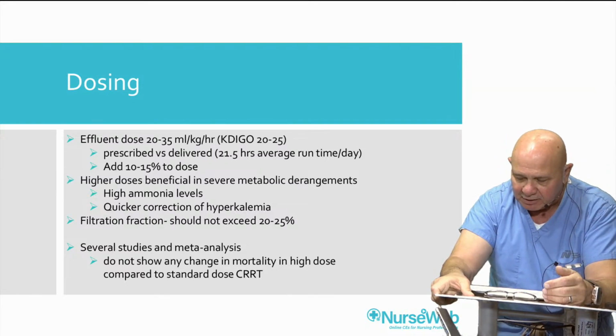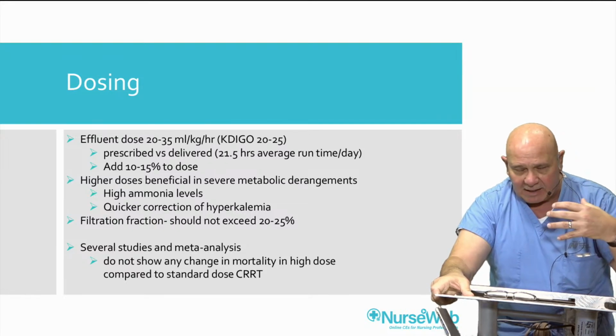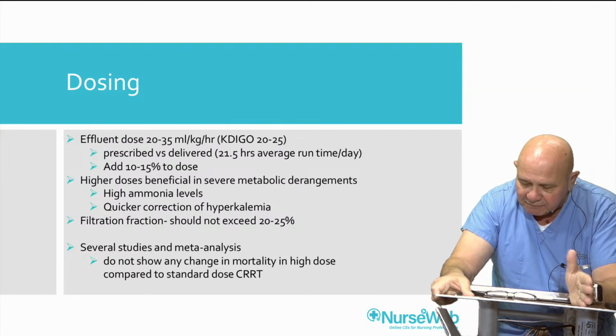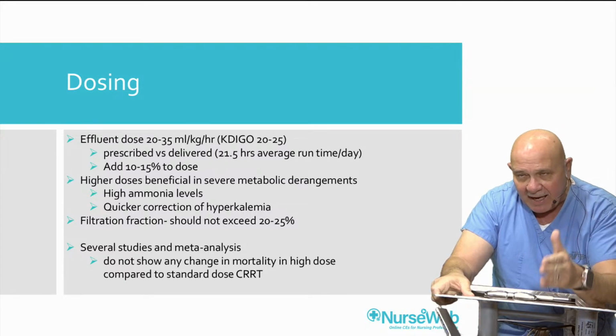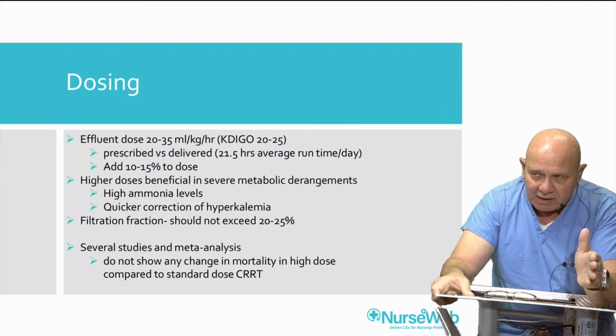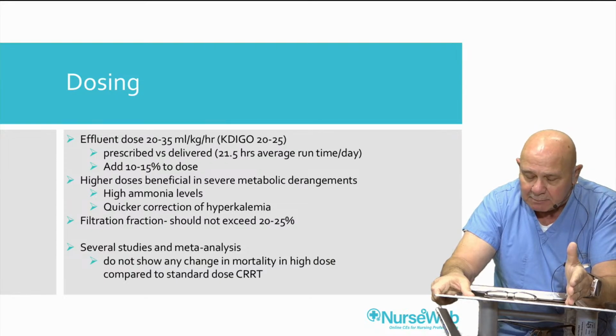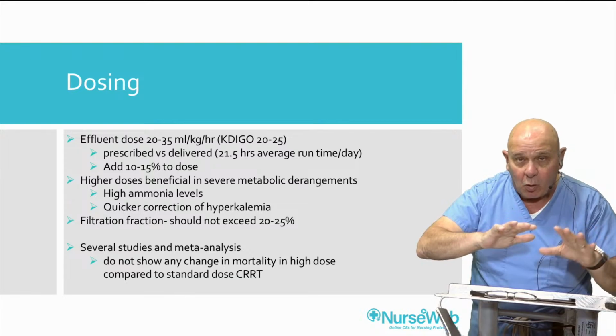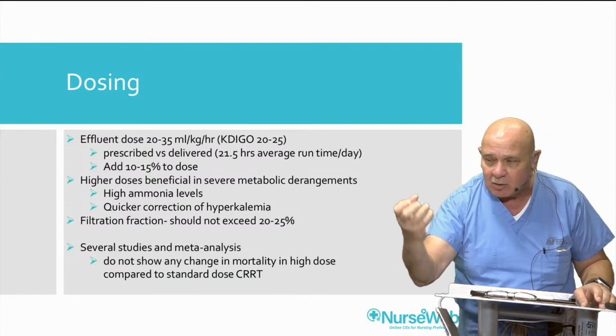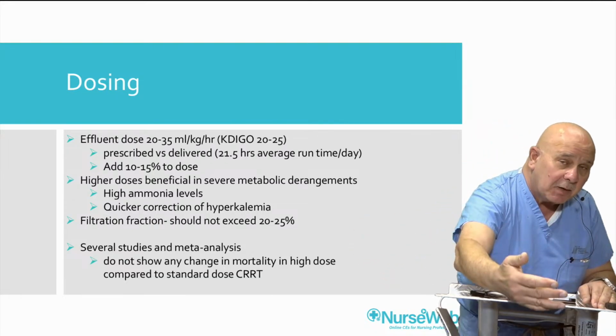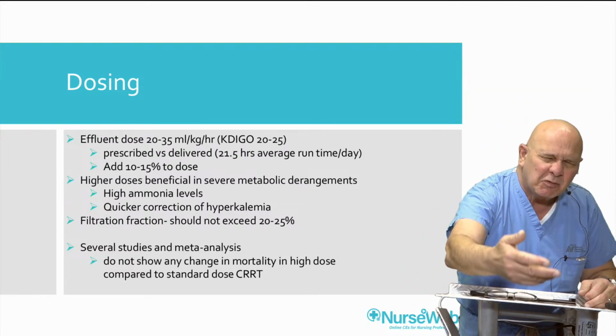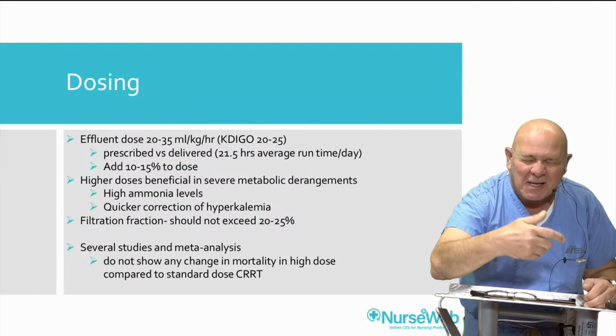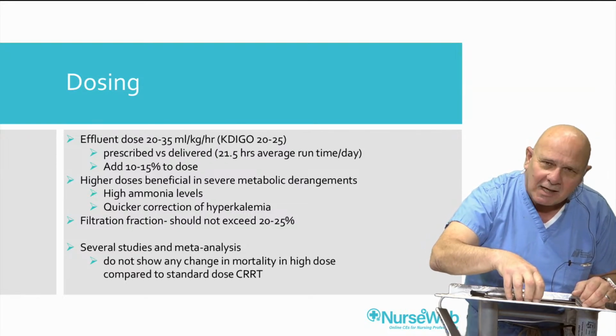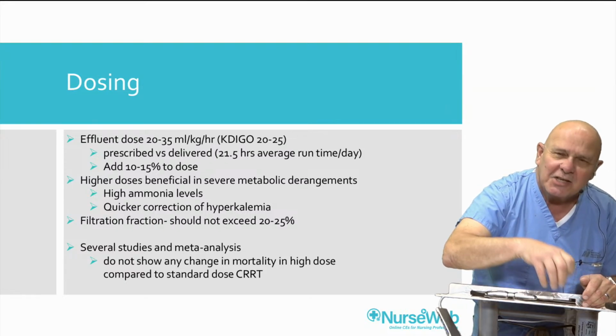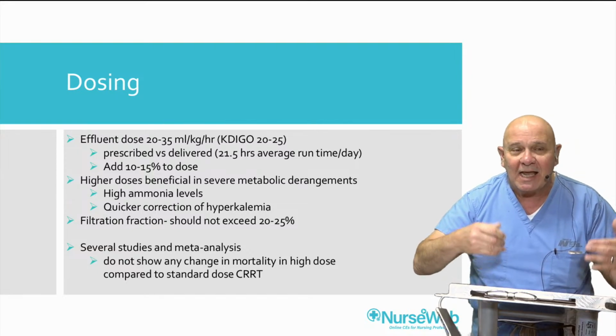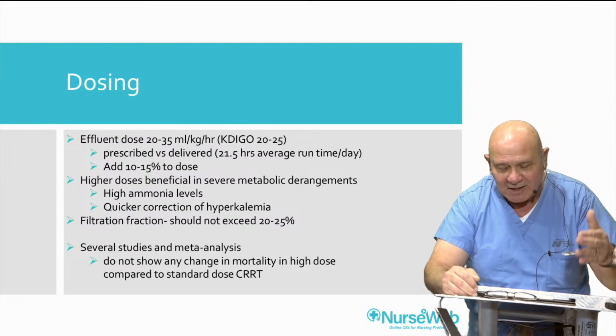Now, what is the filtration fraction? Well, the filtration fraction represents, in human physiology, the proportion of the fluid that gets to the kidneys that passes into the tubules. So in the CVVH world, there's a big long formula. I'm not going to go over the formula with you. But basically, remember I said whole blood is going into a filter, and you're removing the plasma water or a portion of it. The more of that you remove, that's the filtration fraction. If I take 20 or 25% of that plasma water, it makes the blood thicker. Thicker blood is going to pass more slowly through the filter, and you run the risk of clogging it. So to keep your filter healthy, you don't want a filtration fraction to be more than 20 to 25%.